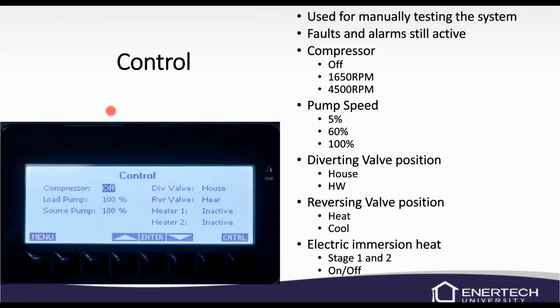The control, when you get into this control mode, it's used for manually testing. So here you can turn your compressor either off, set RPM at 1650, which is the lowest, or at 4500 RPM. Pump speed, you can change it accordingly, 5, 60, 100%. Diverting valve position, you can change it to house or hot water, your reversing valve position, and your electric immersion heaters. It'll tell you what's going on with those, what position they're in, and things like that.